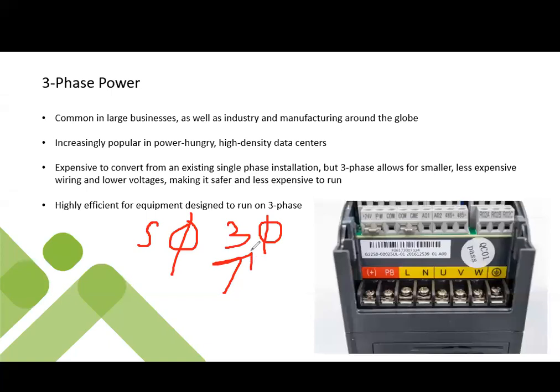Well, very economically, what we can do is purchase a VFD. And with that VFD, we can bring single phase into the variable frequency drive, and it will give us three phase out. And it does that with electronics. We're not going to be using a magnetic field for that. The magnetic field will already have been produced by the utility. And all we're going to do is bring single phase into my drive instead of three phase.